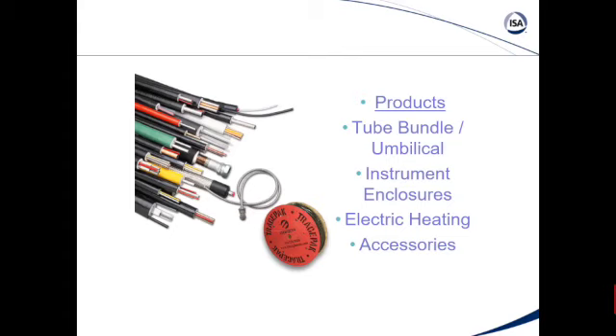So one great option is what we call a preheat traced and insulated tube bundle, which is basically we get in early and we understand what your specification for tubing is, what you want to maintain, all the typical stuff that we do for the piping. But what we would provide is one product. The product is the tubing that you need, the heat tracer, the insulation, and an extruded polyethylene or PVC jacket on the top of that. How that would typically be done in the field is a guy would run your tubing, terminate your tubing. Another guy would come along, apply the heat trace, terminate that. Another guy would come along, insulate, wrap it all up, and paint it with mastic. So you have a lot of people touching the pipe who aren't really working together. They're different trades.